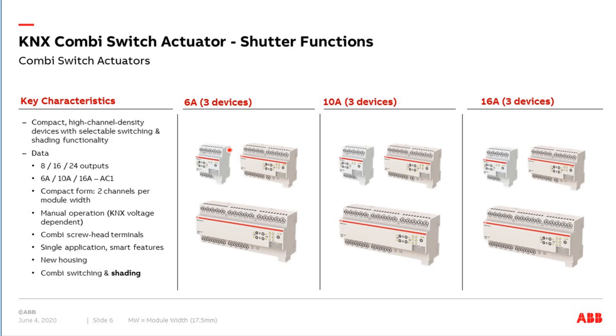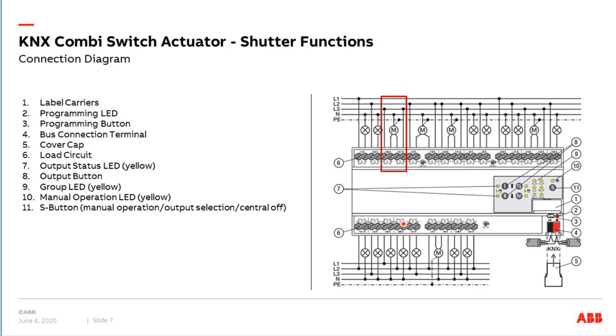We talk about the KNX CombiSwitch Actuators — in total nine devices: three with 6 ampere, three with 10 ampere, and three with 16 ampere. The rest — manual operation, connection terminals, housing — is largely the same. We have from 8 over 16 to 24 outputs for switching. For shutter, the number of channels is half of that, because it's a Combi device you can use for switching but also for shutter solutions.